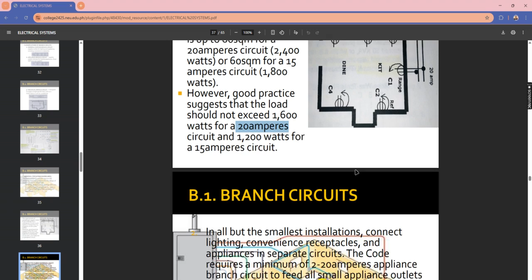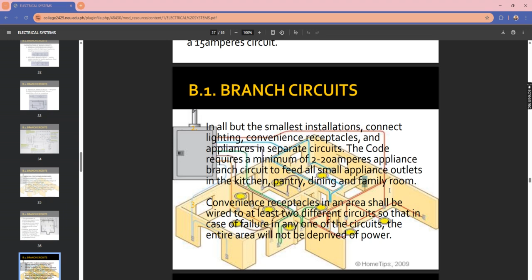In all but the smallest installation, connect lighting, convenience receptacles, and appliances in separate circuits. The code requires a minimum of 2 20-ampere appliance branch circuits to feed all small appliance outlets in the kitchen, pantry, and dining. So, tama lang yung 20 amperes, no? Dalawang 20 amperes.